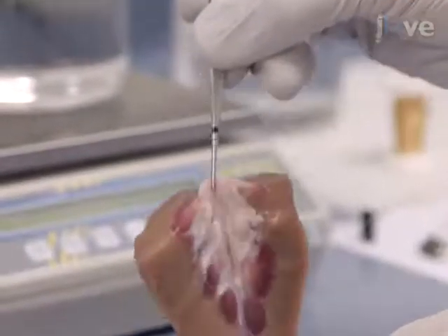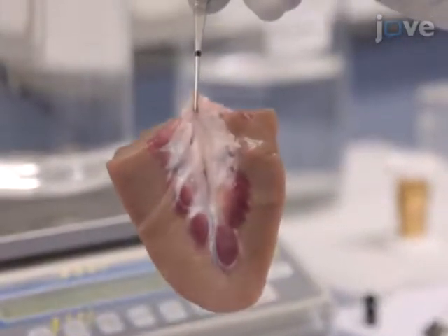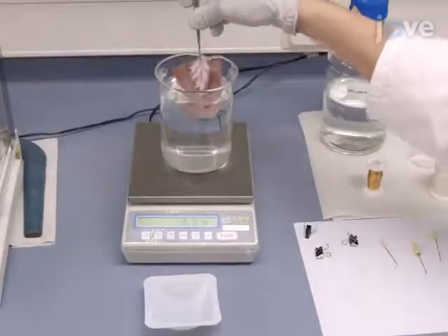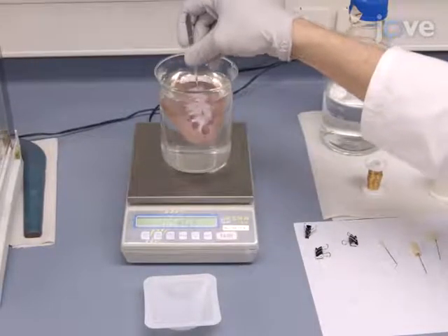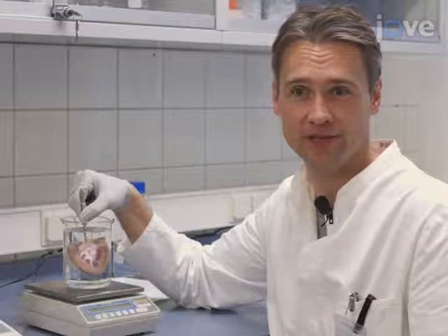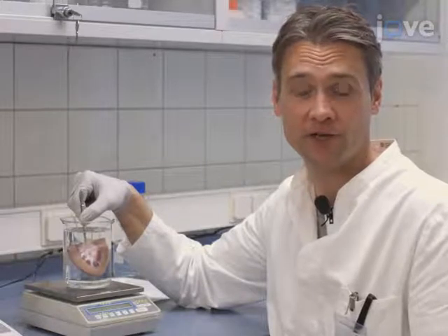Carefully attach the tissue sample to the forceps or sample holder and completely submerge the sample in the saline until the marked position is reached. To record reliable density measurements, it is important to ensure that the sample is completely submerged and to avoid any contact of the submerged sample to the inner walls or the bottom of the beaker.